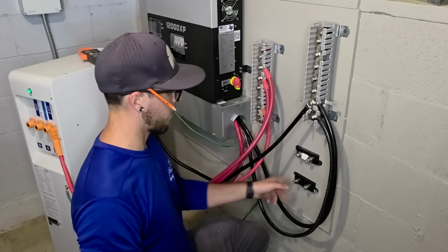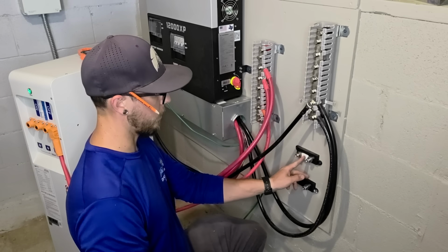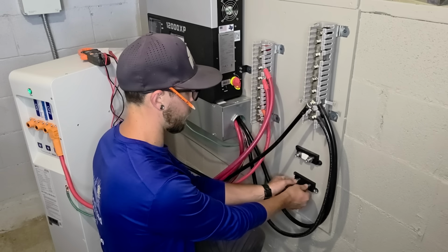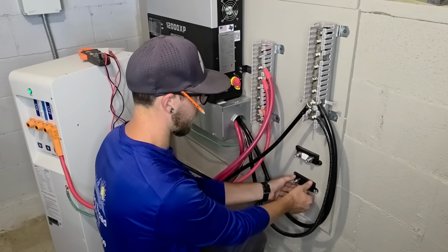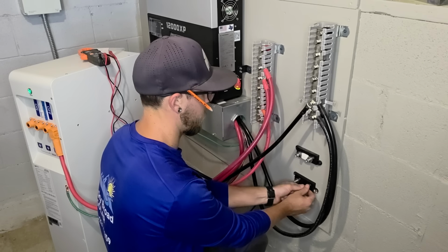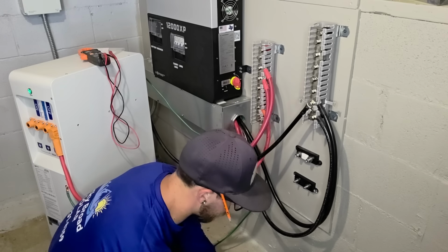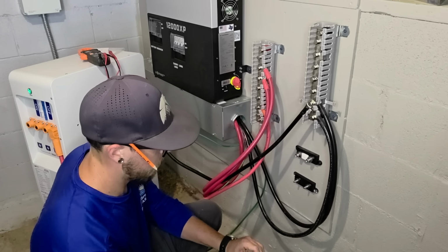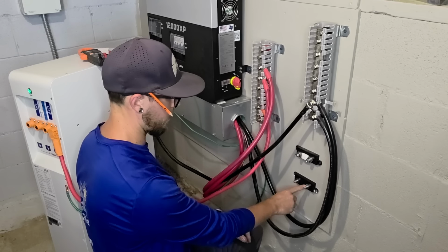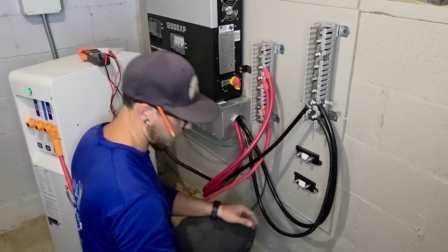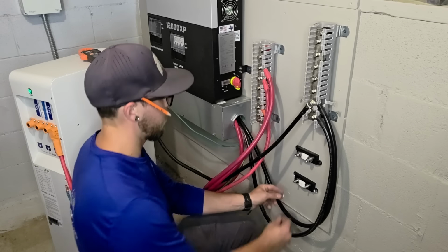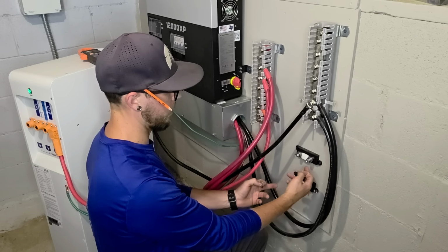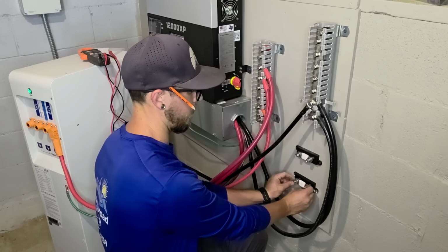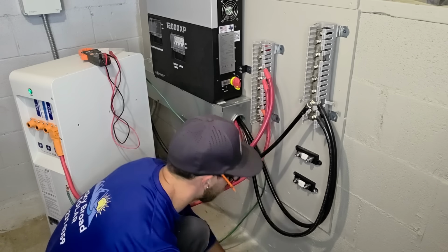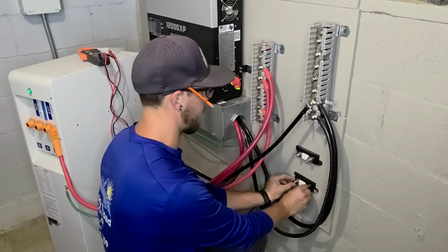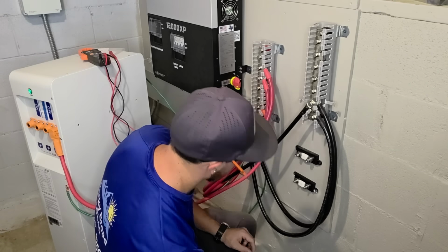I want to point out the order that we layer everything is very important. What we want to do is make sure that our fuse is laying on top of the washers here. Then we'll connect our cables. We'll put a washer over the cable, a split washer to keep it from backing out, and finally our nuts.